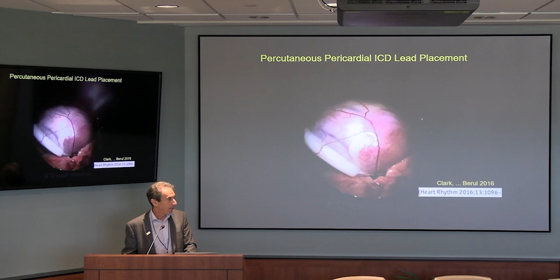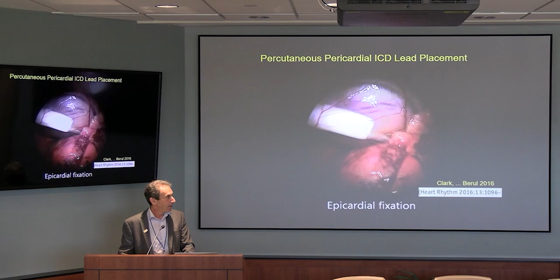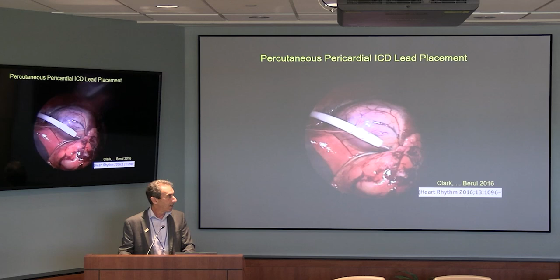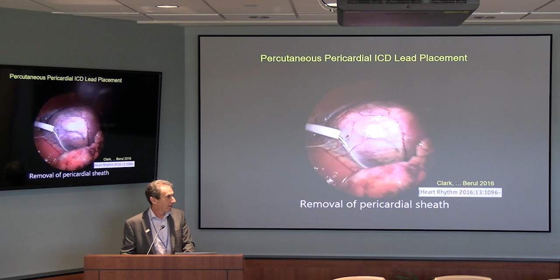The needle's out, and it's just a plastic sheath in there now. And we can put a defibrillator lead and wrap it around the heart. By just rotating it, we fixate the defibrillator lead to the heart, pull out the sheath through that little port, and that's the end of the procedure. You can see just a little small hole in the pericardium, which is fine. You don't even need a pericardium. You can take the whole thing out, but it's just a little hole in the pericardium, and this whole procedure takes less than an hour.